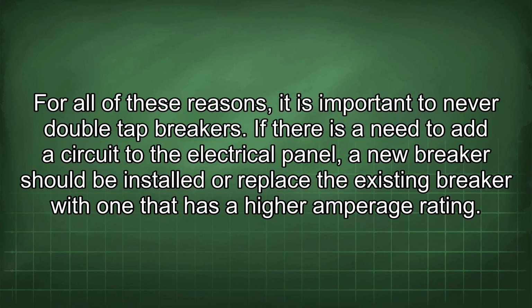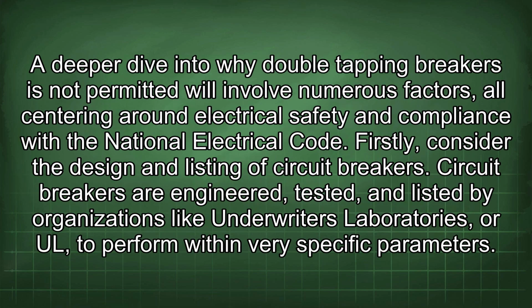If there is a need to add a circuit to the electrical panel, a new breaker should be installed, or replace the existing breaker with one that has a higher amperage rating. A deeper dive into why double tapping breakers is not permitted will involve numerous factors, all centering around electrical safety and compliance with the National Electrical Code.